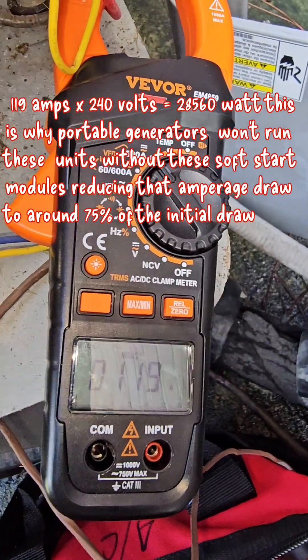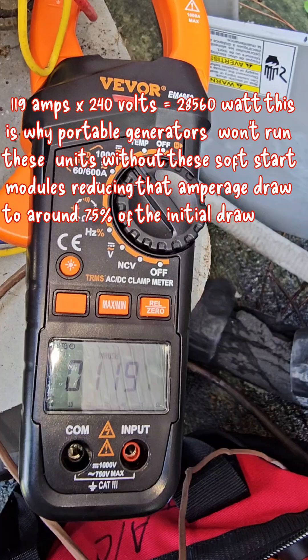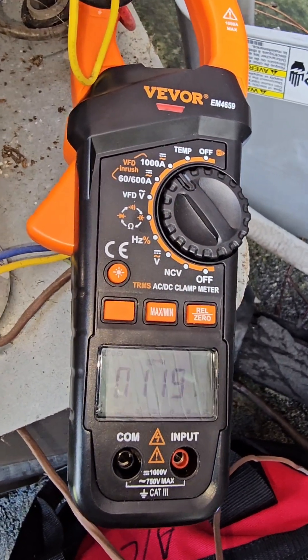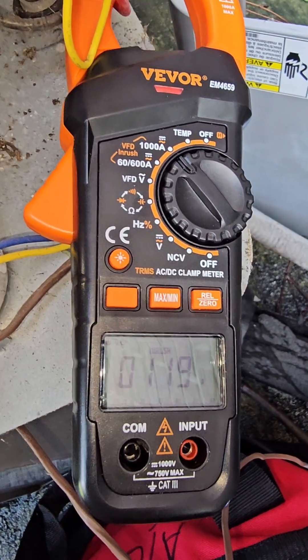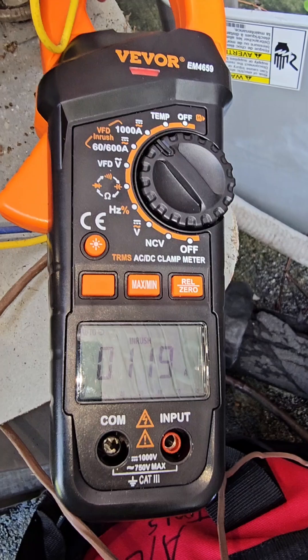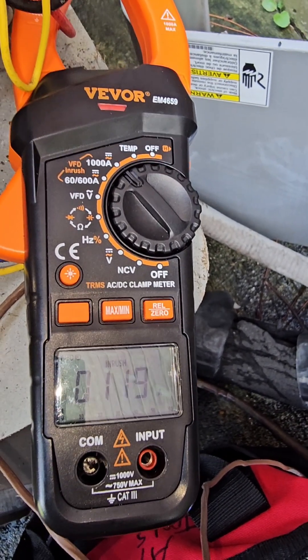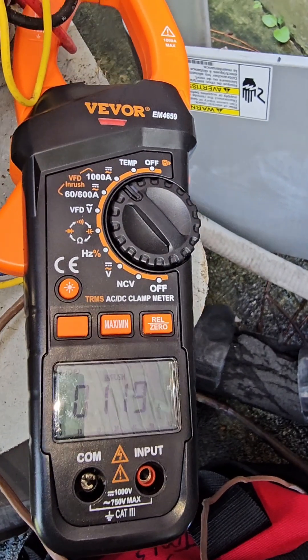This is how many amps a Furrion unit, or my Furrion Coleman unit, draws at the initial start-up — what they call an in-rush. Now if you were to add the soft start module to this unit, where you can use a portable generator to run this unit, it would drop those amps significantly, where your 30 amp generator would be able to power this unit.